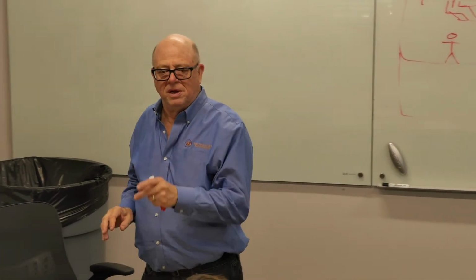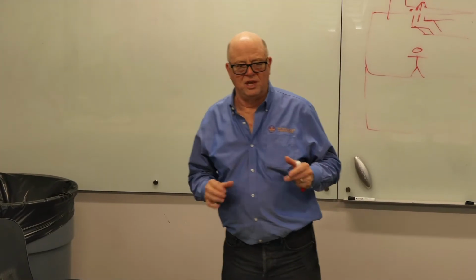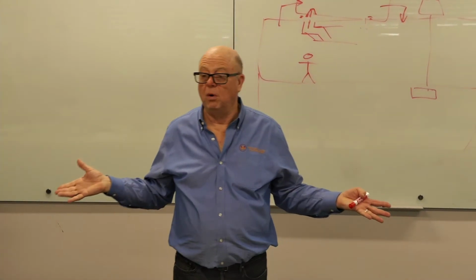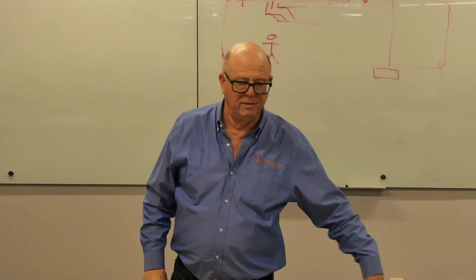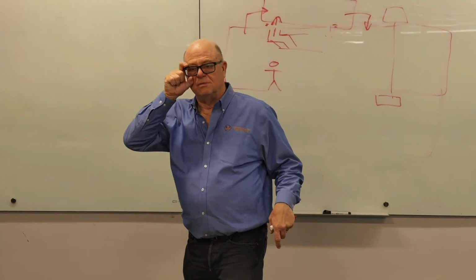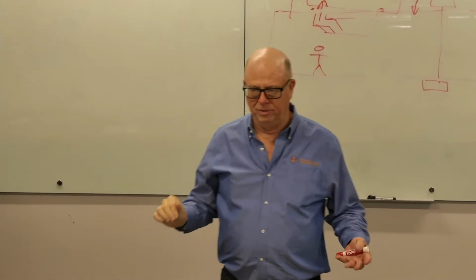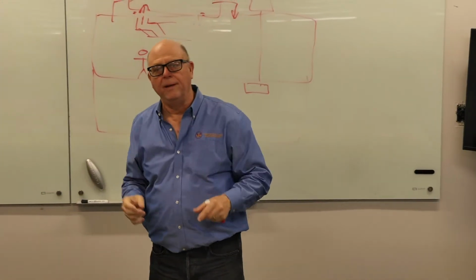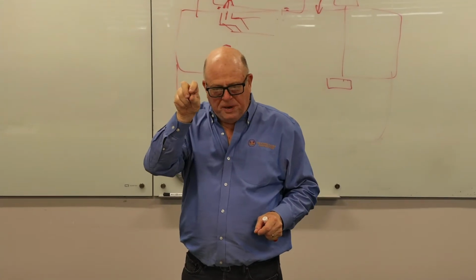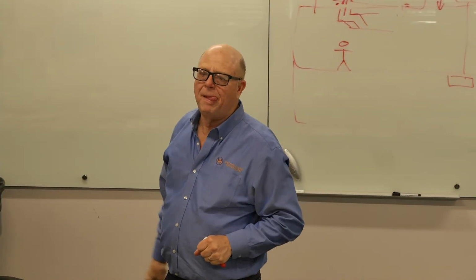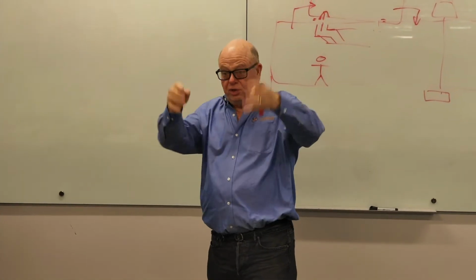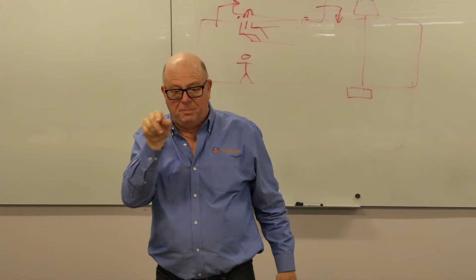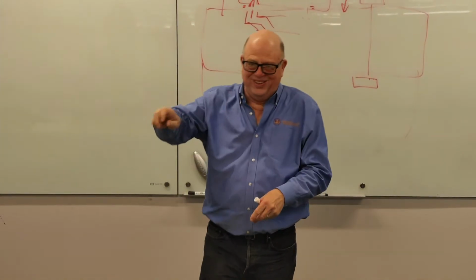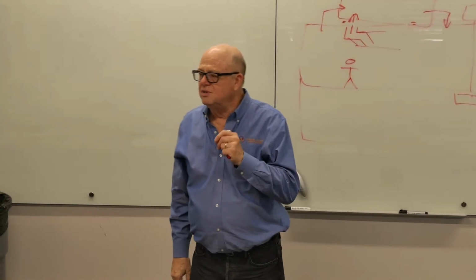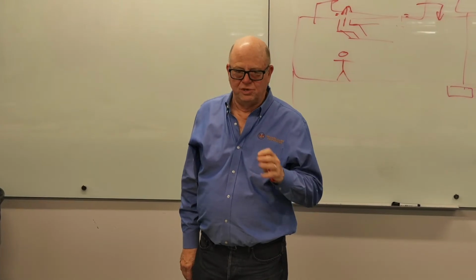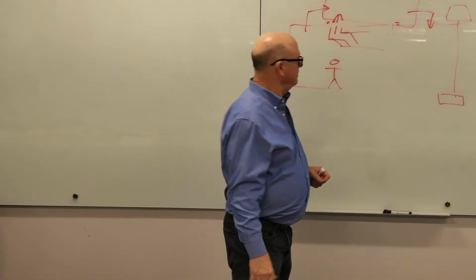They wanted to be exhausting as much air from the hot corner of the server room as they could, which did get the temperature down to where they wanted it to be. They were pulling air in from everywhere. Nobody ever sealed the conduit entering that room, so they had plenty of ability to pull air in. And they basically just dialed the speed down until it got to where the sound engineer was happy. And we ended up at 40%. Now, we could have done the little cheap one-elbow sound boot, and maybe he would have been down at 20% or 10%, but we wanted him to be able to do as much as they could. So sometimes this is not terribly scientific. Sometimes you're just kind of pulling it out of somewhere on your anatomy. And that's what we did.